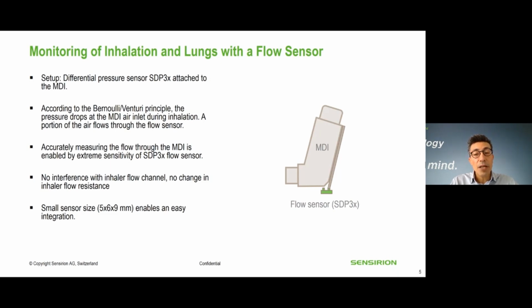According to the Bernoulli-Venturi principle, the pressure drops at the MDI inlet during inhalation. A portion of the air flows through the flow sensor. The extreme sensitivity of the sensor SDP3x gives an accurate flow that correlates to the inhaled airflow through the MDI. By doing so, we created no interference with the inhaler flow channel, and we caused no change in the inhaler flow resistance, so that the drug delivery would not be impacted by the flow measurement.